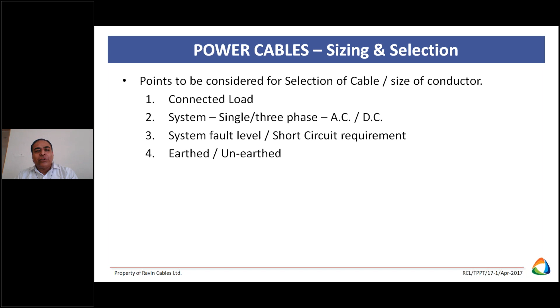For selecting a cable, ultimately, first what do we want? We want the following points to be considered. First, what is the connected load? Suppose the connected load is 100 kilowatt. What is the system? Single phase or three phase system, AC or DC? Whether the system is earthed or unearthed, that is also required. What is the fault level current? What is the short circuit requirement? Because your protection devices will operate on your short circuit requirement.